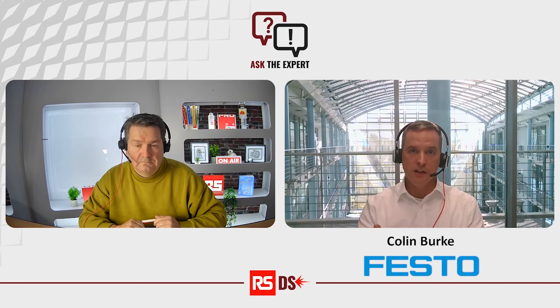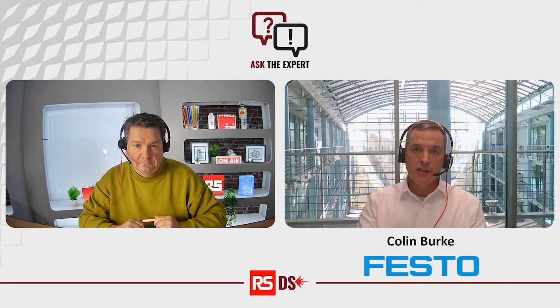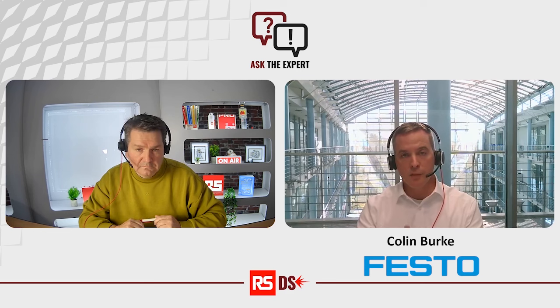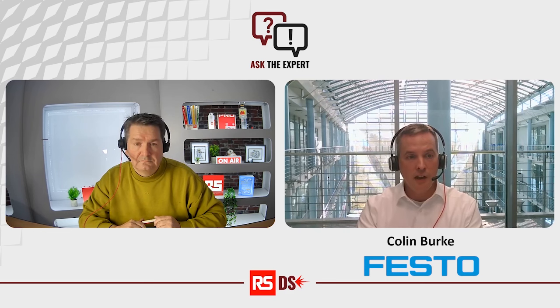They take less space in the cabinet. The high power ones, they use silicon carbide technology. What does that mean? They don't run as hot. We're not wasting as much energy. You need less cooling in your cabinet. You can even go for a smaller cabinet, and you've got DC linking, so you can get energy recuperation. So the physical cables are set up that you just, with very small cables, link them together, and they're smart enough to accept energy coming from the application.